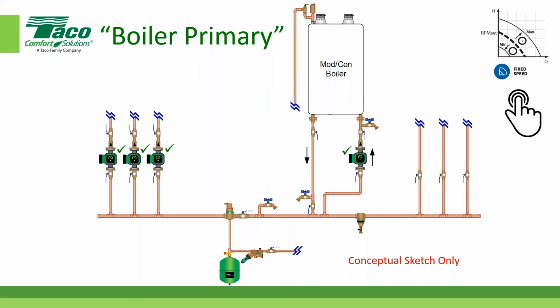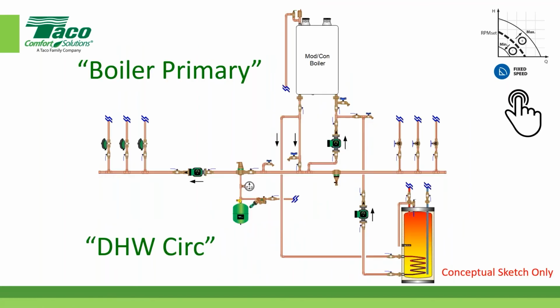So what I mean by sharpening your pencil when it comes to sizing of this particular circulator is size it based on the job at hand. That means at the altitude, at the required amount of BTU delivery for the job, etc. That's what leads these boiler circulators to be oversized, just shooting from the hip, using 20-degree delta Ts, etc. So anyway, hopefully I beat that horse enough.